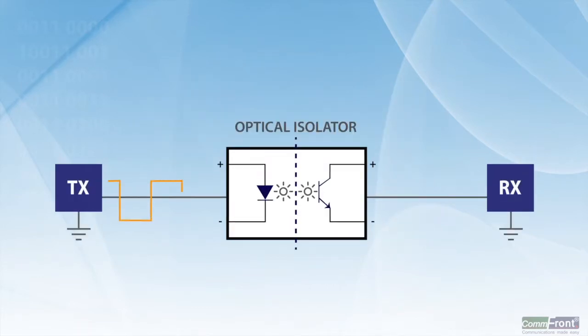In other words, data is transmitted using light instead of electrical signals, so there is no physical connections between both sides, including grounds and data lines. Thus, removing the problems of noises, remote lightning, sparks, voltage surges, and ground loops, and effectively preventing electrical surges and spikes from destroying other parts of the system.